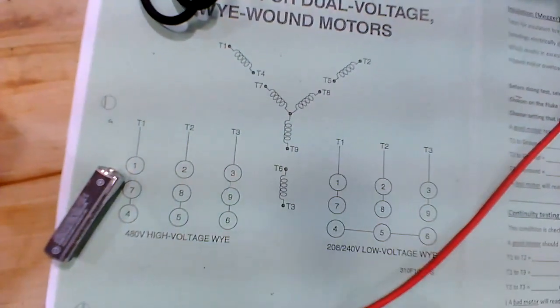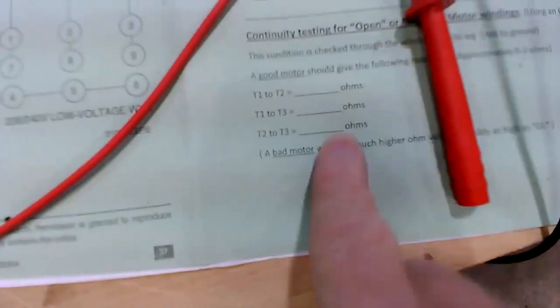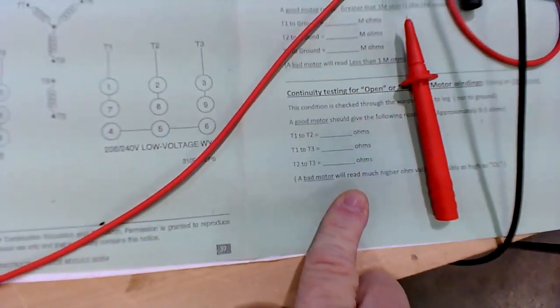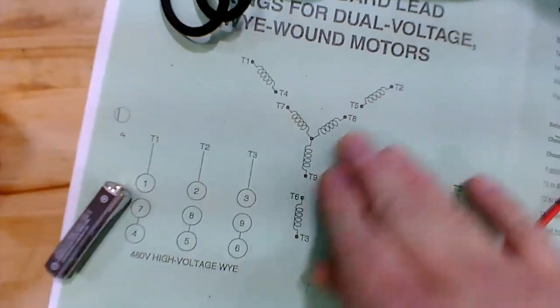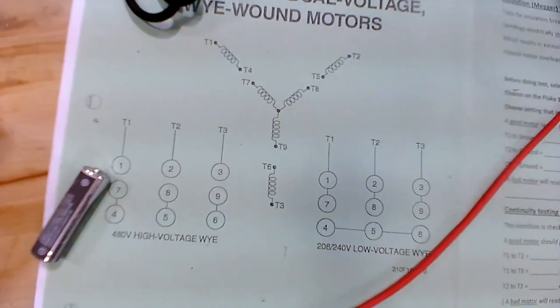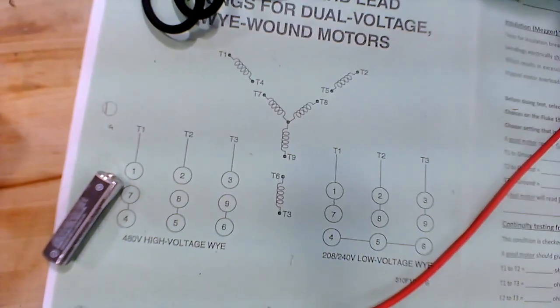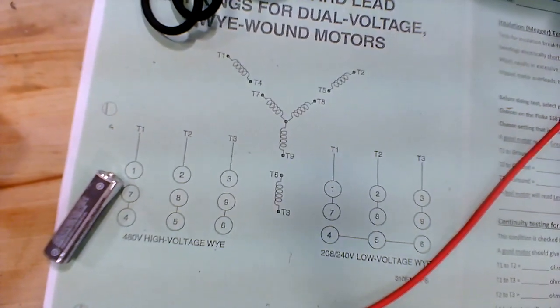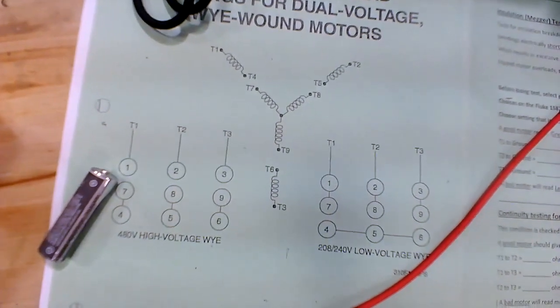So whatever the resistances are, they should be balanced. Those 3 readings should be very similar to each other. That makes sense? And if they are, then the windings are in the same condition, or I would consider them to be healthy windings. You don't have one of them that's kind of breaking down and the other ones are okay. You don't have a bad imbalance there.